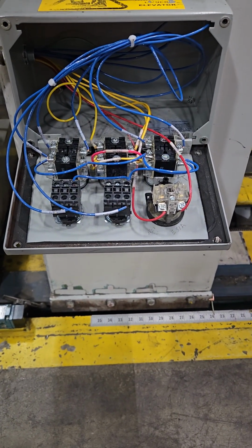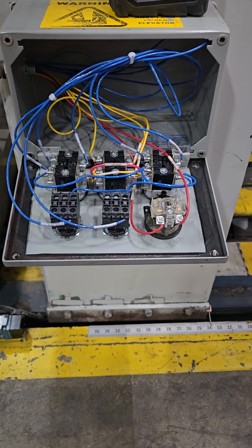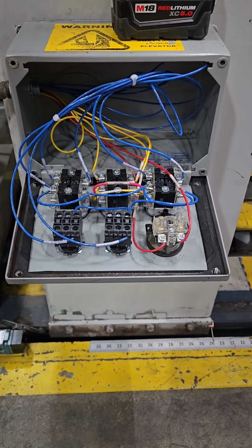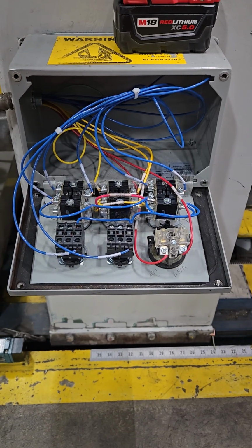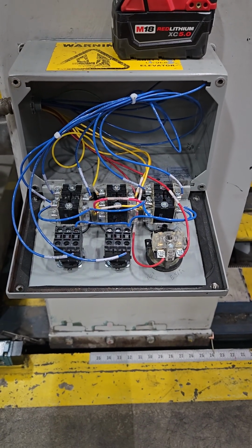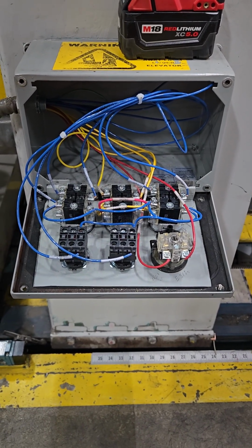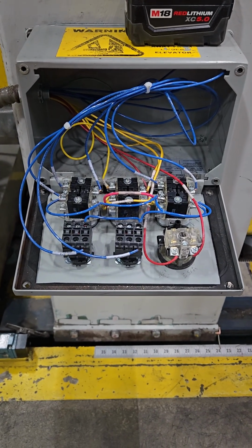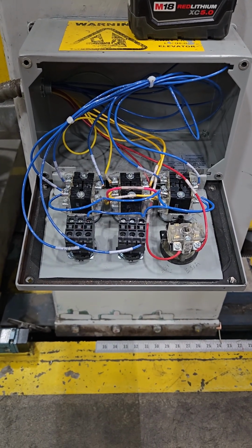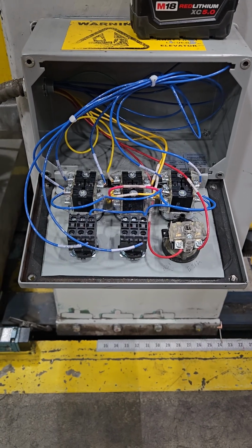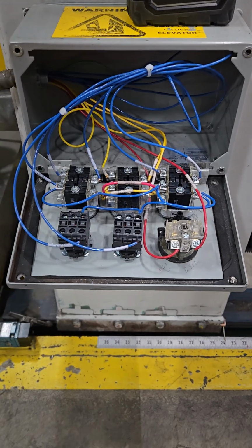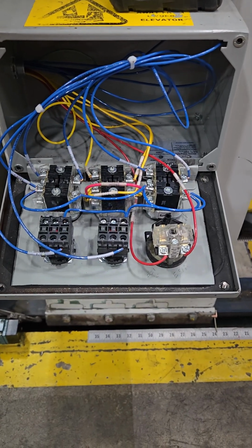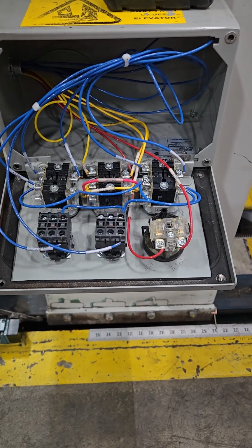With this upgrade, it is to be more effective in use and for troubleshooting. As you can also see, it has less clutter of wiring. Also, it is partially to be safer with 24 volts DC than having 120 volts AC. And a side lesson is when you see yellow wiring, it means foreign or external power. So still be careful, knowing that although the blue 24 volts DC is off, the yellow wire can still potentially be live.